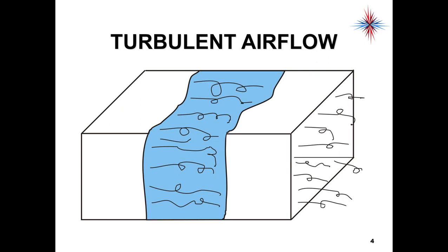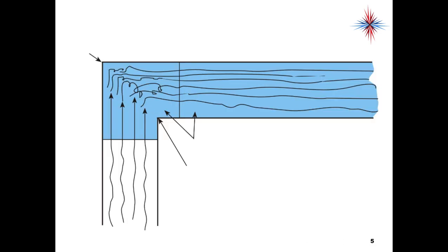Turbulent flow means that the air tumbles and swirls, mixing it up. Almost all airflow in ductwork is turbulent. Turbulent flow mixes the air temperatures, keeps it more evenly spread. However, turbulent airflow increases friction and dynamic loss. Too much air turbulence can cause noise as well.